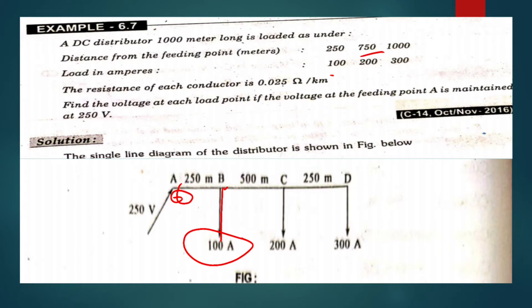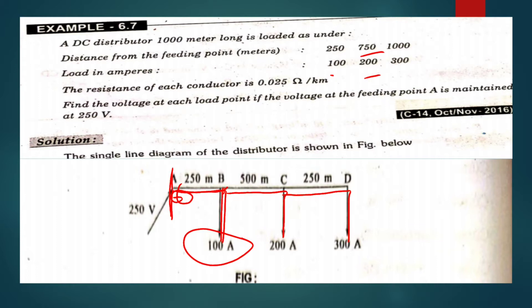At 750 meters distance we have 200 amps of tapping. So we have a starting point at 250 meters with 100 amps tapping, and between B and C the distance is 500 meters. At the 1000 meter end point we have one more tapping of 300 amps.